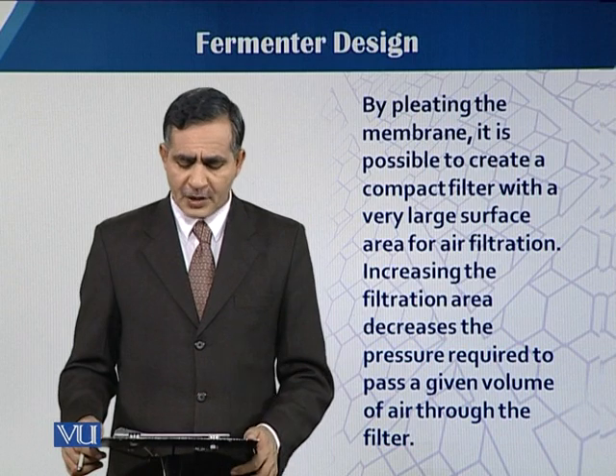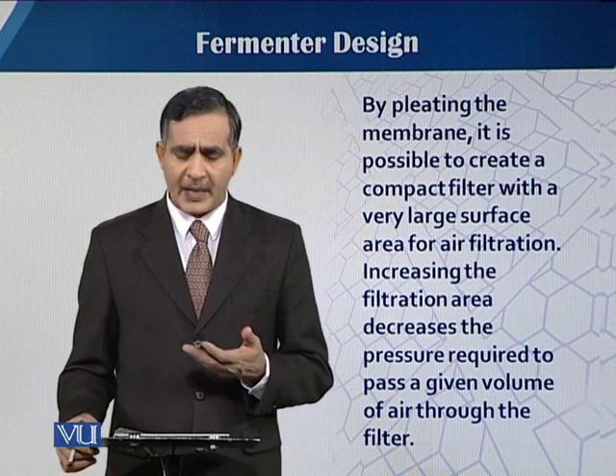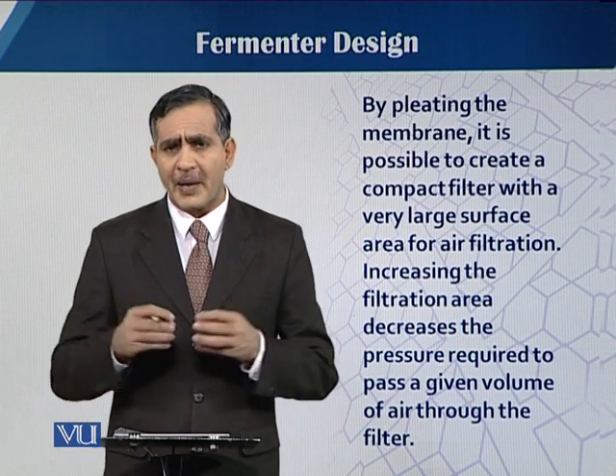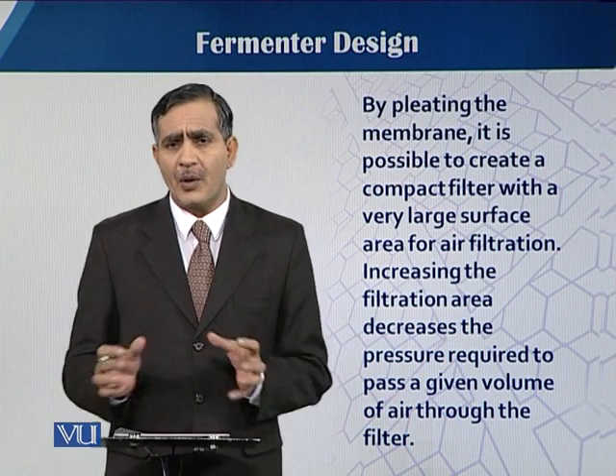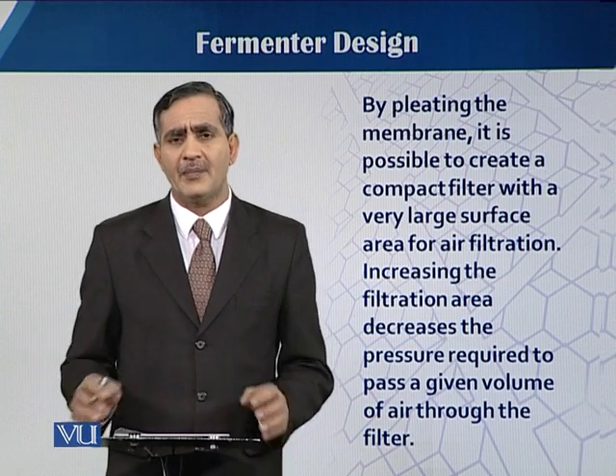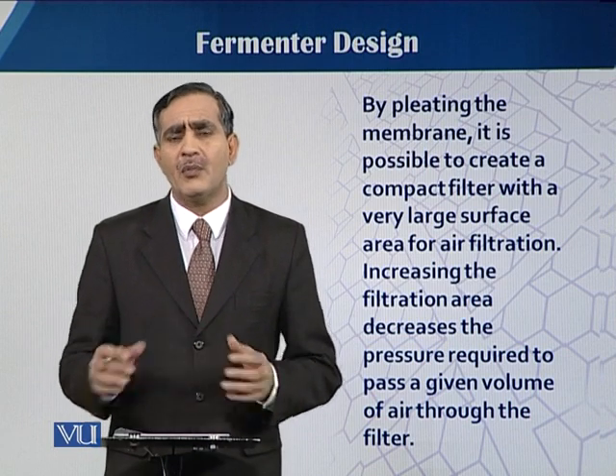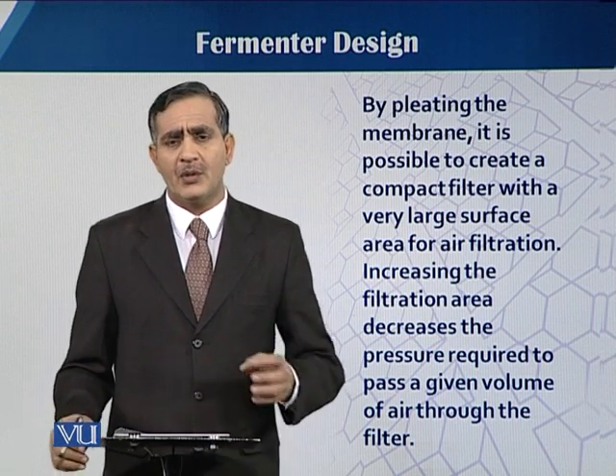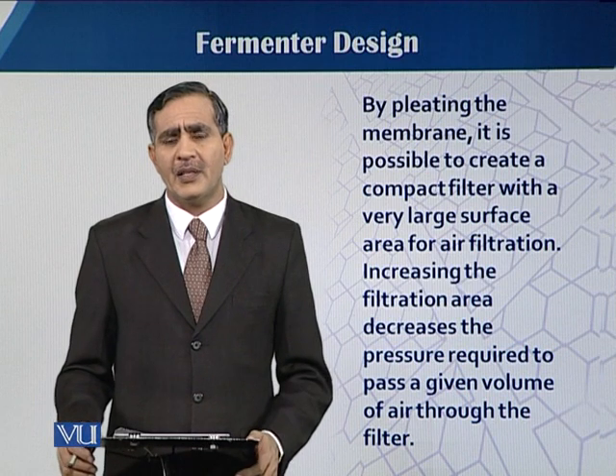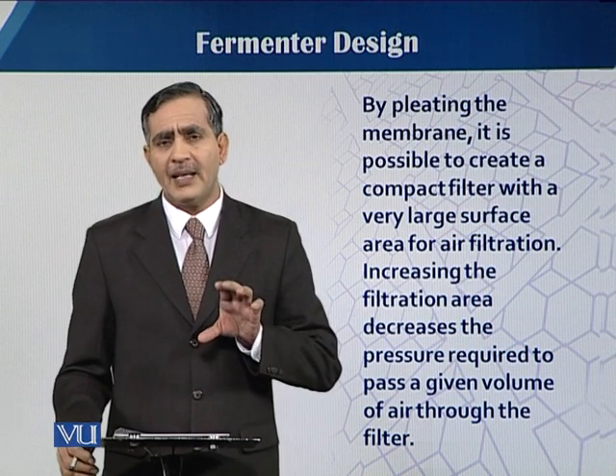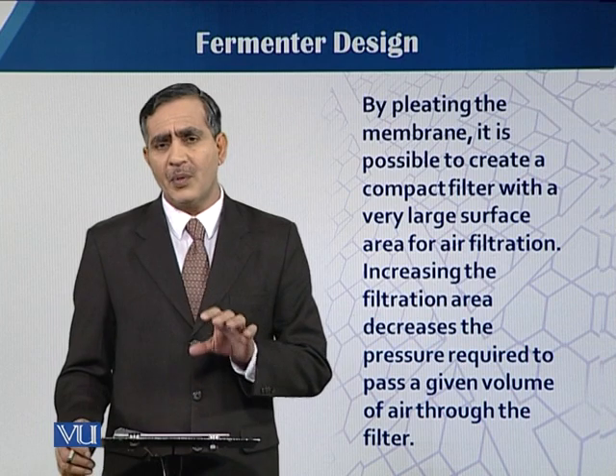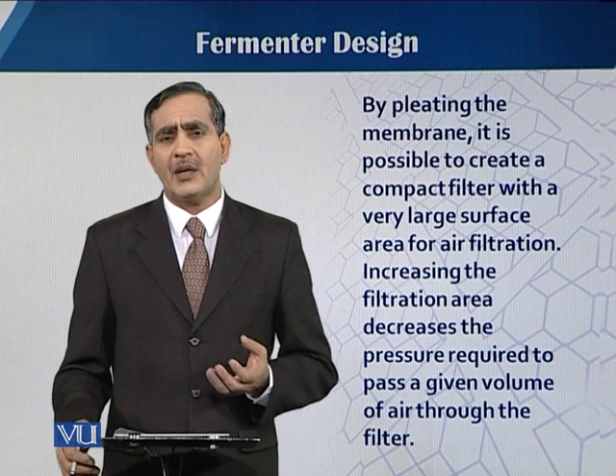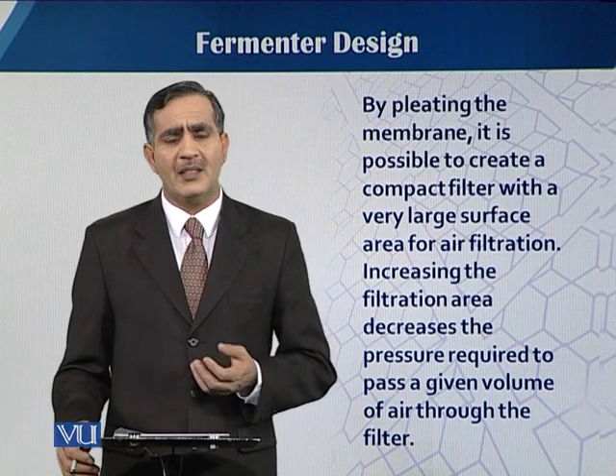By pleating the membrane it is possible to create compact filters with a very large surface area. When the teflon membrane is compacted inside the polypropylene housing, it creates maximum area — the greater the area, the less pressure is required to pass air through the filter. If the filter is very tight with less area and fewer pores, the air quantity required for fermentation is not sufficient.